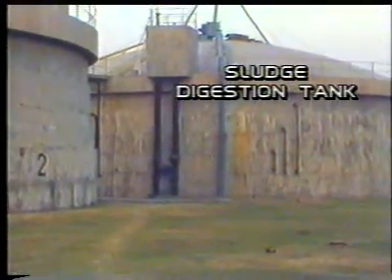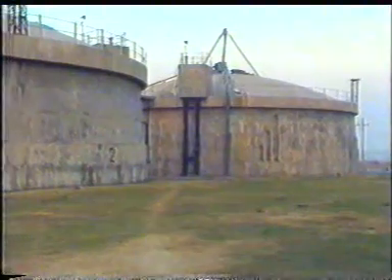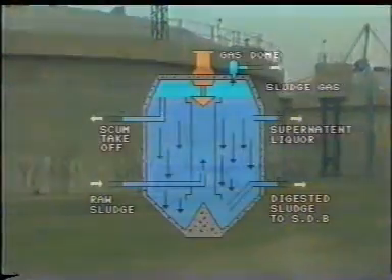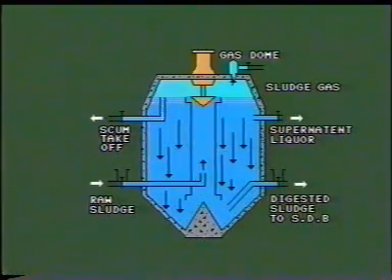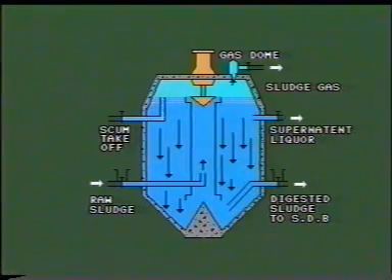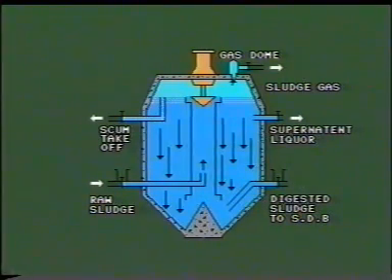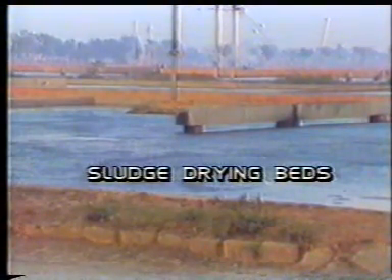Sludge is passed on to the sludge digestion tank for anaerobic decomposition of organic matter, a process known as sludge digestion. Raw sludge is pumped into the center of the tank for a detention period of about four weeks. Gases are released through a dome at the top, while supernatant liquor and scum are removed from the tank. Digested sludge settles down and passes on to sludge drying beds. Dried sludge, which is rich in nitrogen, is used as manure.